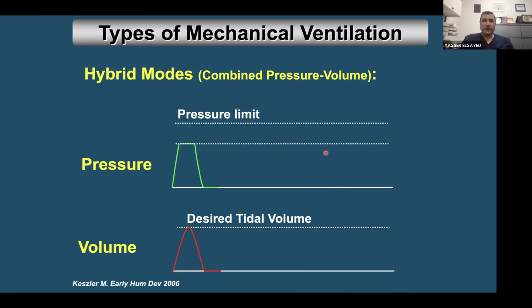So let us please focus with me on this slide to explain what the hybrid mode is and how it works, which is a combined pressure and volume. It is basically pressure limited, but hybrid with volume. So now assume that we have a preset volume, for example, 5 ml per kg, and the machine will deliver the pressure needed. It could be 15, could be 20, based on the compliance to deliver this preset volume.